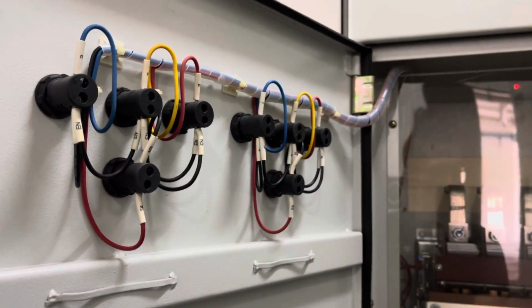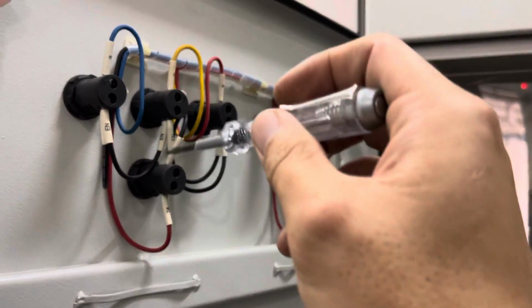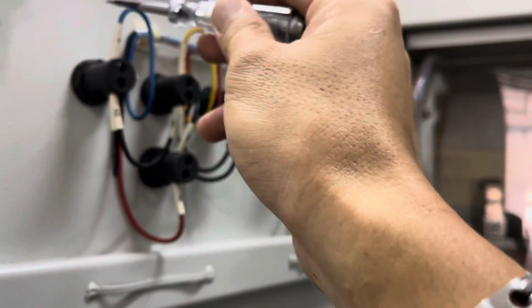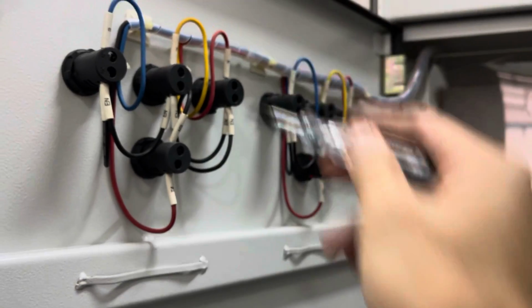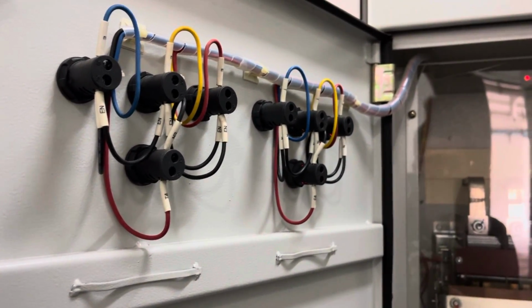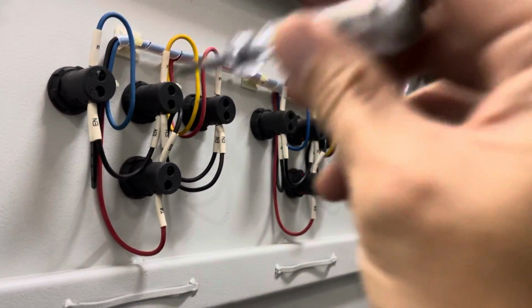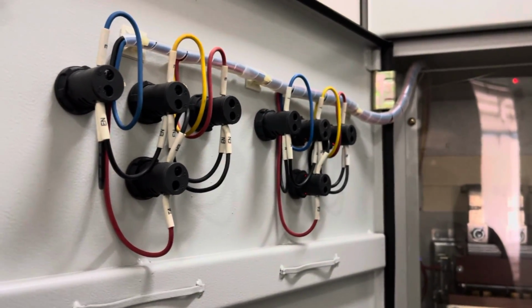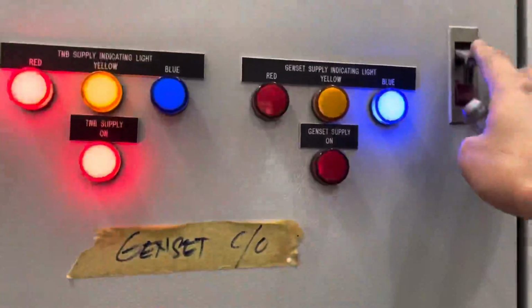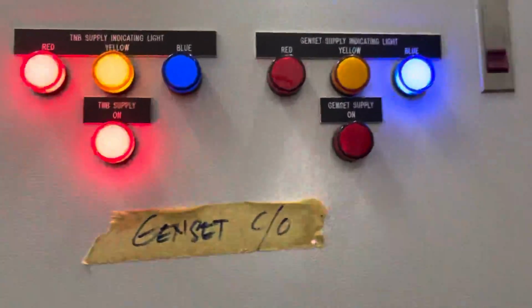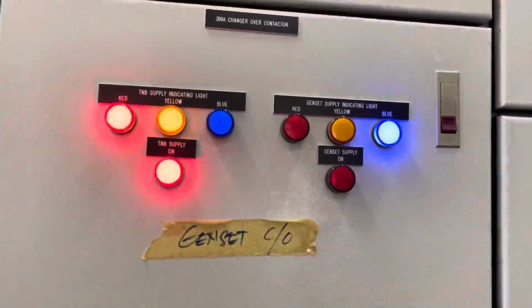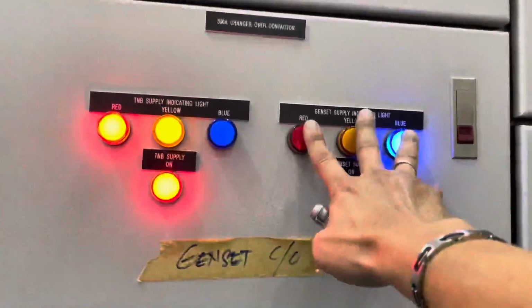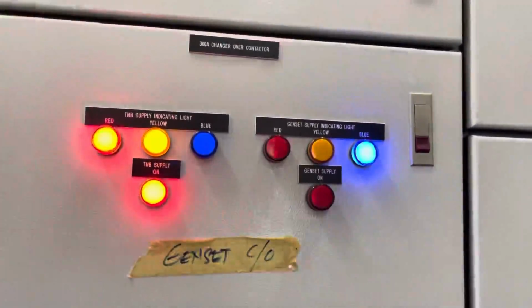Power supply reaches here and there's no tripping from the MCCB side at the AMF panel. And as you check the frequency here, 50 Hertz, that means the genset engine is operating in good condition. That means 1500 RPM. So no issue. And now what we do here, we just need to wait for the genset to stop automatically. After the genset stop automatically, everything will be back to normal.